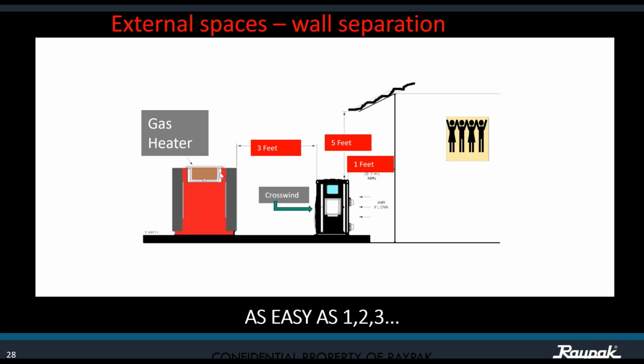Okay, if your installation is going to have also a gas heater, make sure that you are 3 feet away from each other. Why? The gas heater is going to need air for combustion and ventilation. But at the same time, the Crosswind is a lateral air discharge and it's going to be expelling cold air, but at the same time, it's going to be taking air from the ambient. So both of those appliances need air for their proper functioning.